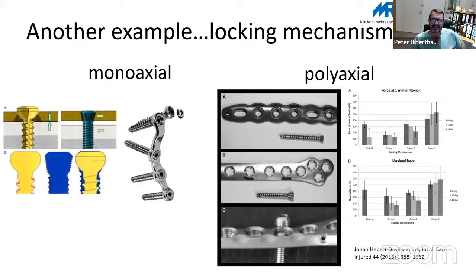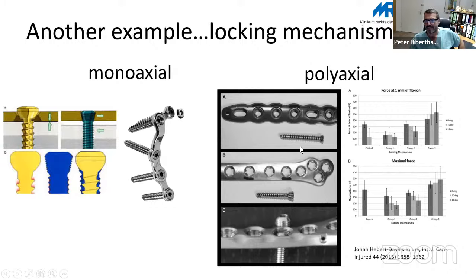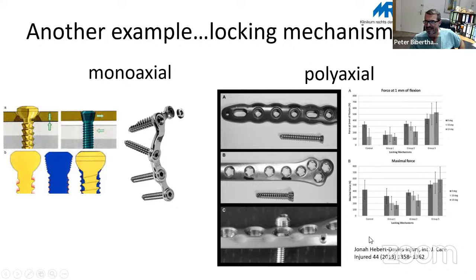Another example: locking mechanisms. Locking screws came up about 25 years ago. On the left-hand side you see mono-axial locking mechanisms, and on the right-hand side poly-axial locking mechanisms. You might think that all types of poly-axial locking mechanisms give the same strength, but this is not true — there is a really significant difference between the load and failure power needed to dislocate screws in these three types of implants.